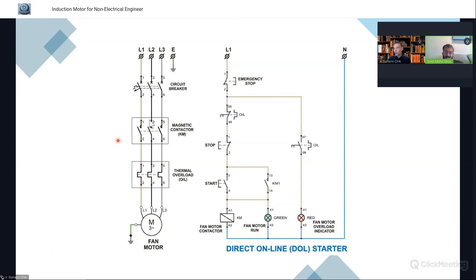Okay. For the protection, we have protection for the short circuit. Short circuit is covered by circuit breakers, so this could be an MCCB. Then for the thermal overload, it will be under this relay, the thermal overload relay. So if anything happens on the load side, it will lock the rotor from turning. Since it is locked, it will increase in heat. When it increases in heat, the thermal overload will operate, without the circuit breaker tripping.